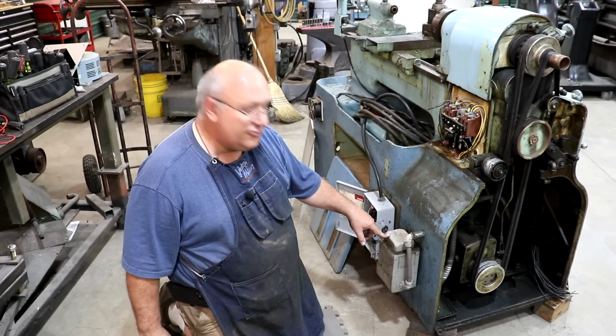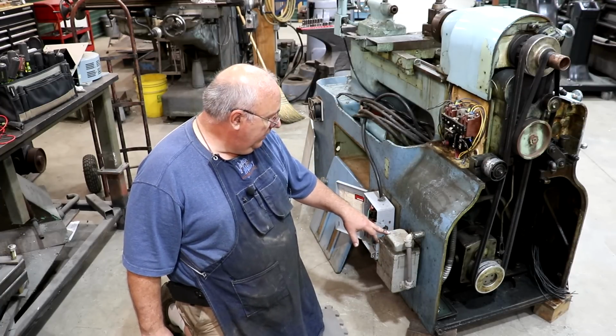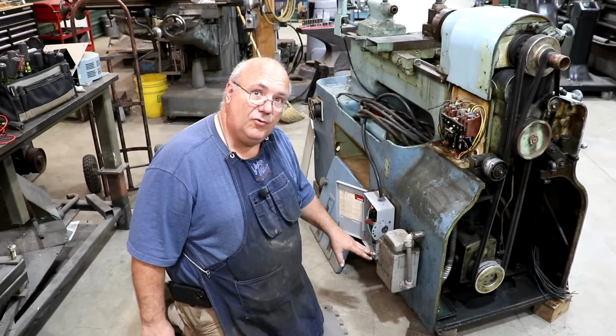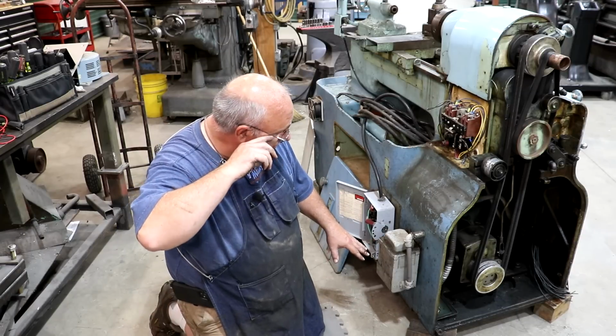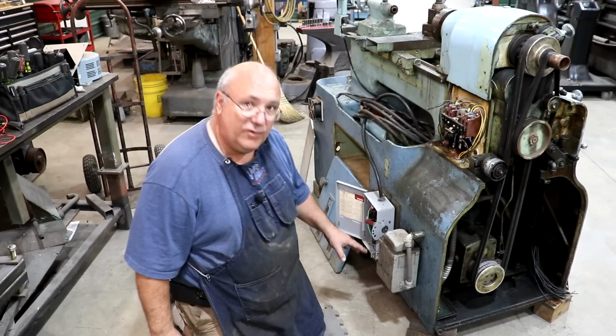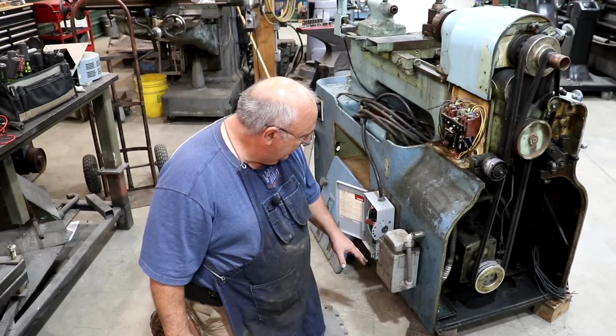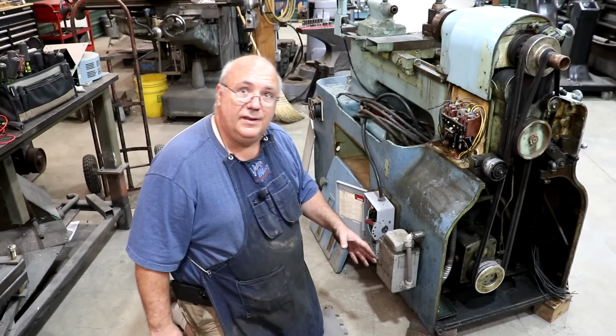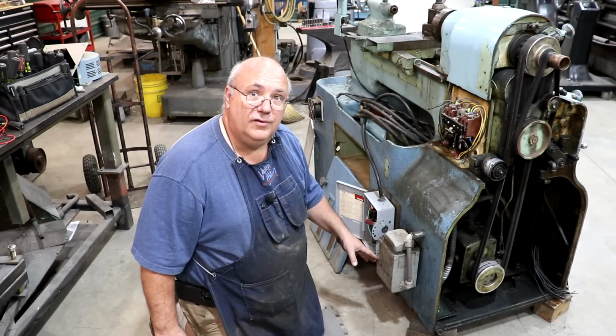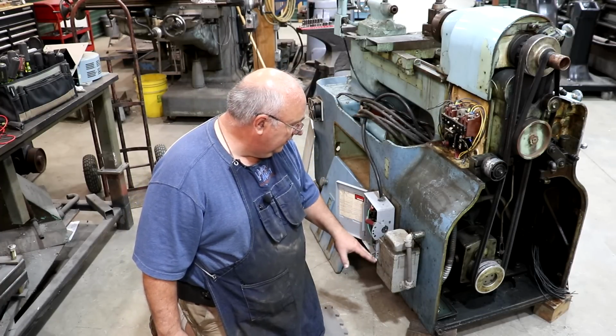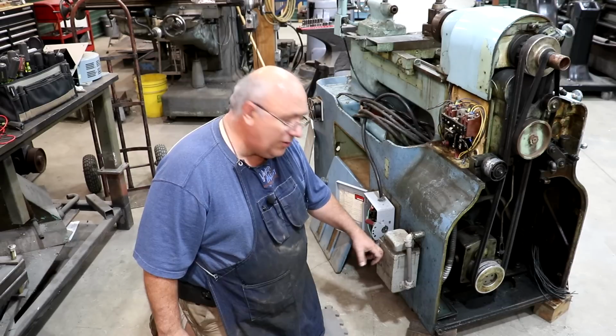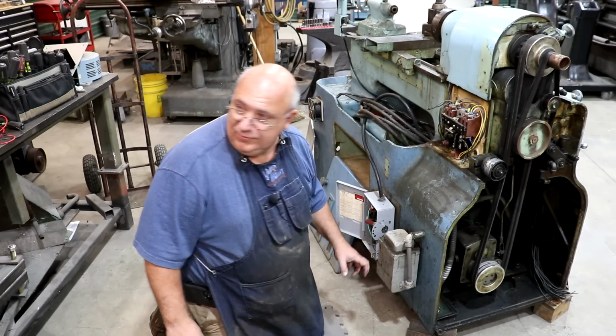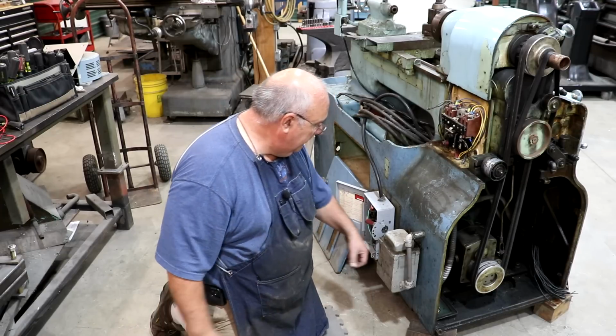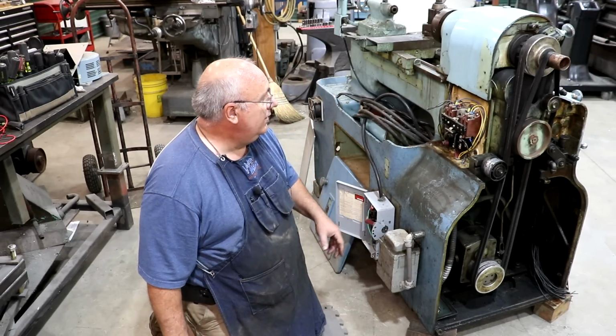I've actually got another control transformer I can put on here. This one did get a little hot when we were testing it out, because we had the wrong voltage hooked up to it originally since we were unclear what voltage it needed to run on. It did smoke a little, but I don't think there was any damage done. I checked it all out and it looks good. I'm going to do a little more checking, and if I need to, I've got another one we can just swap in. But if this one still works, we're probably going to leave it.